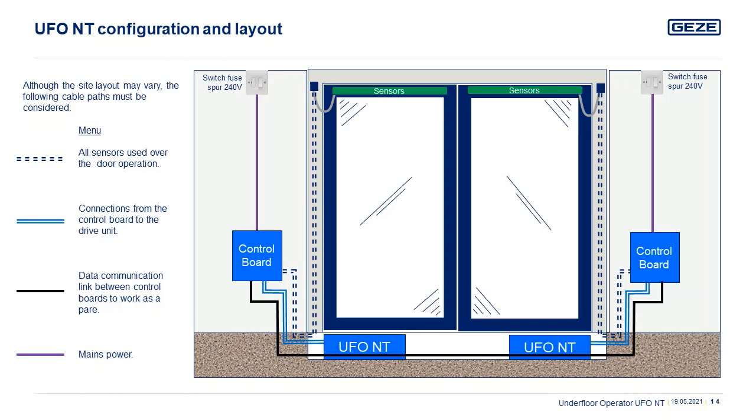Please remember the other activation and controlling devices over the entire door system, such as the DPS program selector, counter switches, push buttons, and break glasses. Local conduit runs as shown may use flexible conduit, but if cables need to travel further afield to a counter location or posts, we advise using a steel conduit. Within the steel conduit path, it will be important that there are no 90-degree bends and a draw wire is left in place.